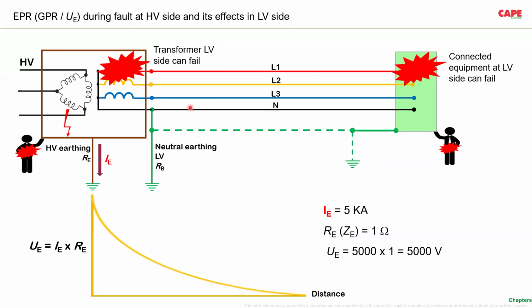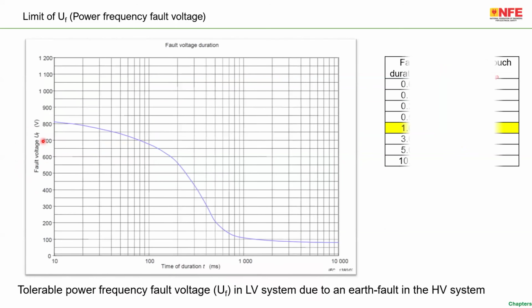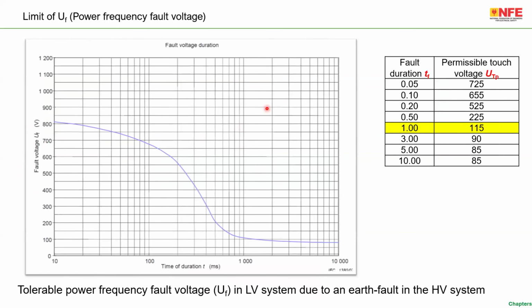That means in the previous slide, if we look, under any condition, a person who is standing in the vicinity or closer to the transformer and touching any metallic parts of the transformer, the touch voltage has to be limited to less than 115 volt if the disconnection time is 1 second, or less than 90 volt or 85 volt if the disconnection time is 3 seconds. That is what we get from this particular chart. This particular table or chart, you will be able to see in IS IEC 61936, IEC 60364, and also IS 732. The same tolerable limit of touch voltage is explained in all the standards.